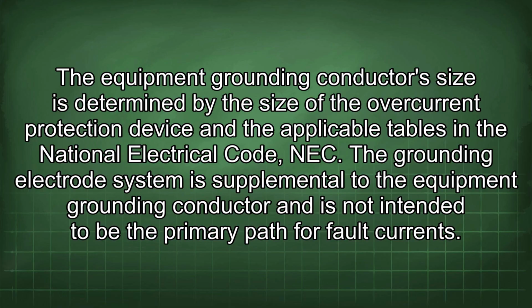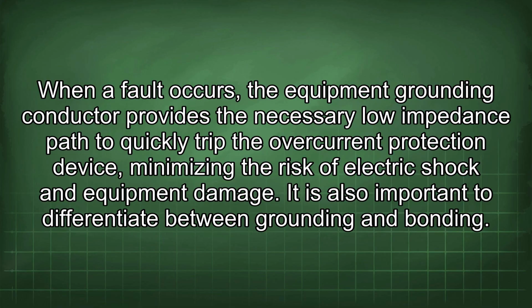The grounding electrode system is supplemental to the equipment grounding conductor and is not intended to be the primary path for fault currents. When a fault occurs, the equipment grounding conductor provides the necessary low impedance path to quickly trip the overcurrent protection device, minimizing the risk of electric shock and equipment damage.